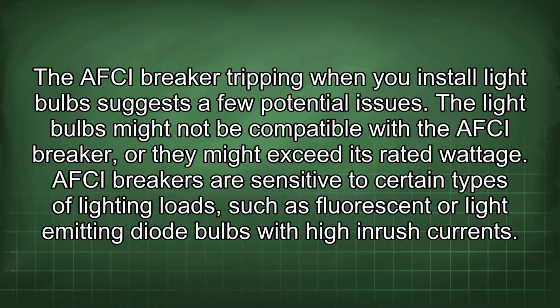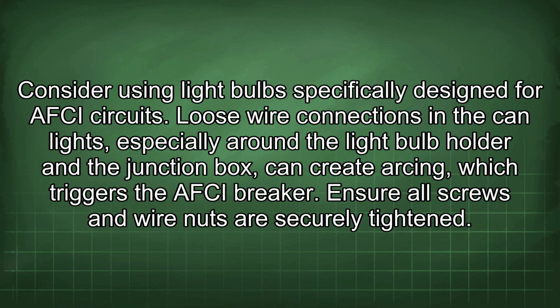The AFCI breaker tripping when you install light bulbs suggests a few potential issues. The light bulbs might not be compatible with the AFCI breaker, or they might exceed its rated wattage. AFCI breakers are sensitive to certain types of lighting loads, such as fluorescent or light-emitting diode bulbs with high inrush currents. Consider using light bulbs specifically designed for AFCI circuits.